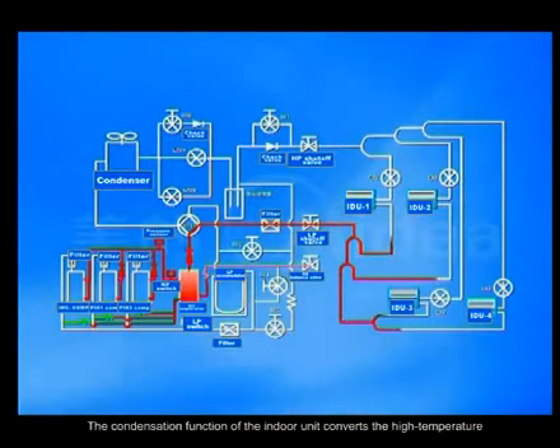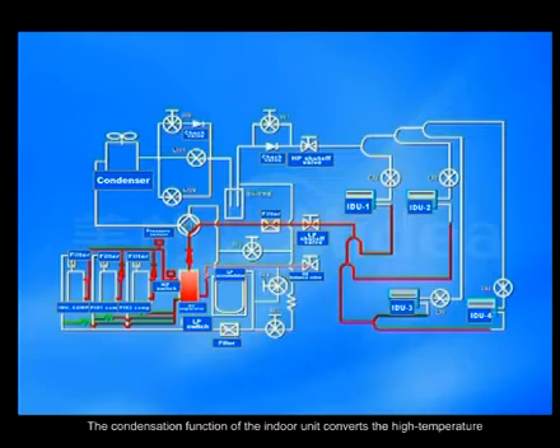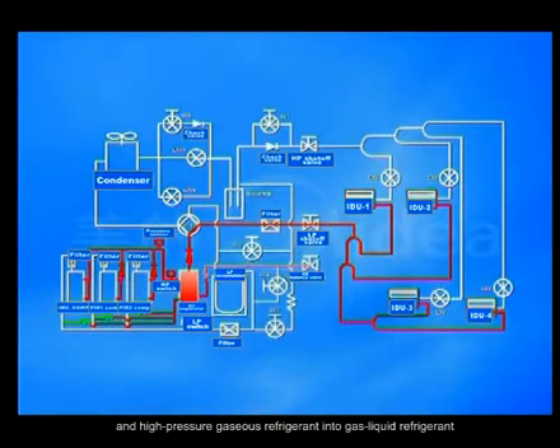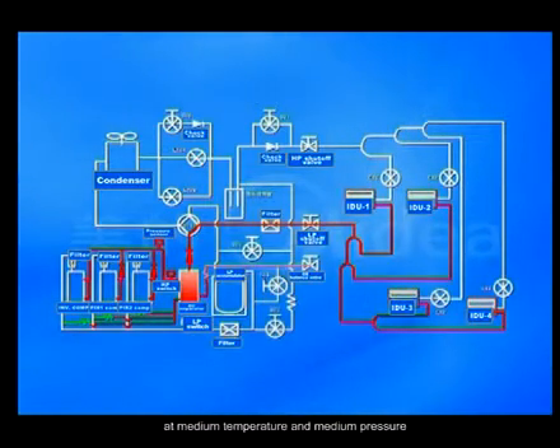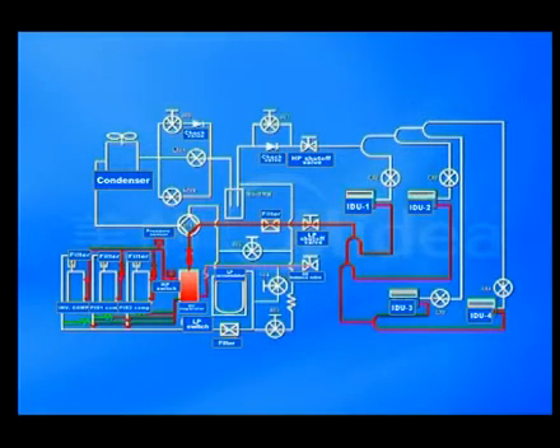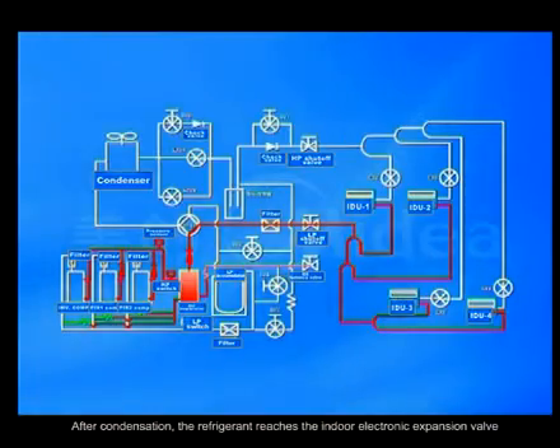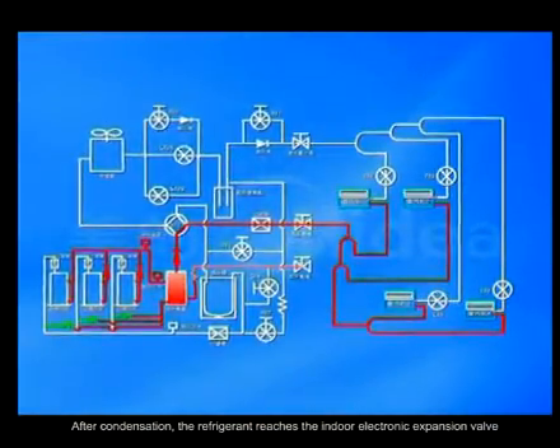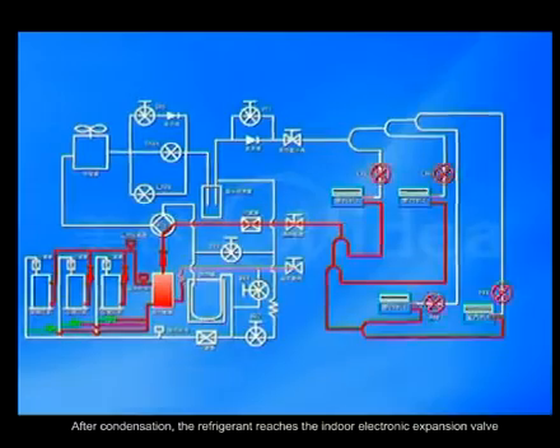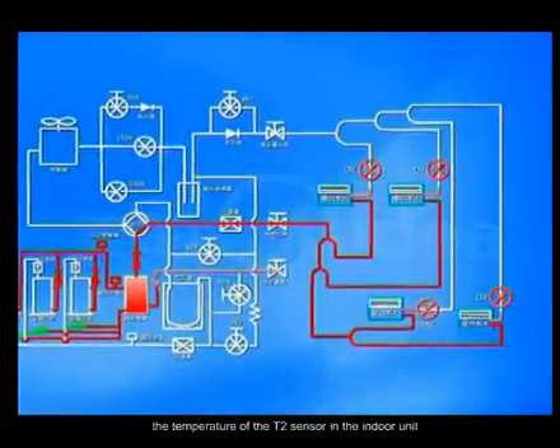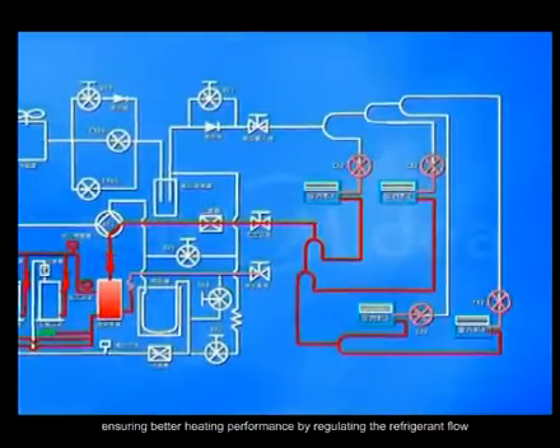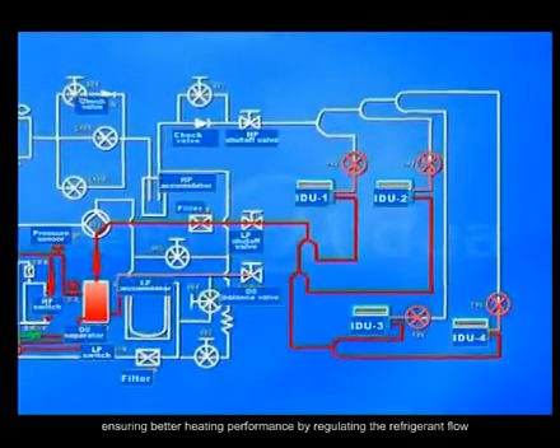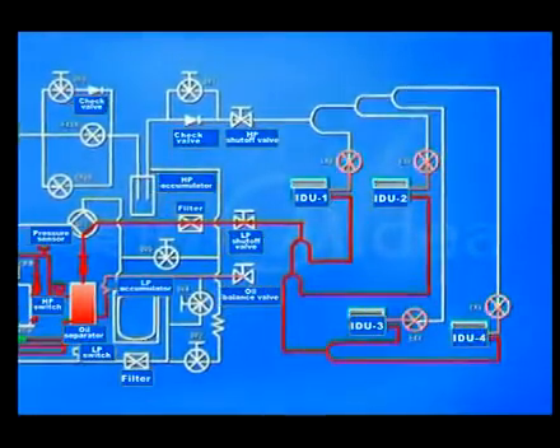The condensation function of the indoor unit converts the high-temperature and high-pressure gaseous refrigerant into gas-liquid refrigerant at medium temperature and medium pressure. After condensation, the refrigerant reaches the indoor electronic expansion valve. The size of the valve opening is adjusted according to the temperature of the T2 sensor in the indoor unit, ensuring better heating performance by regulating the refrigerant flow.